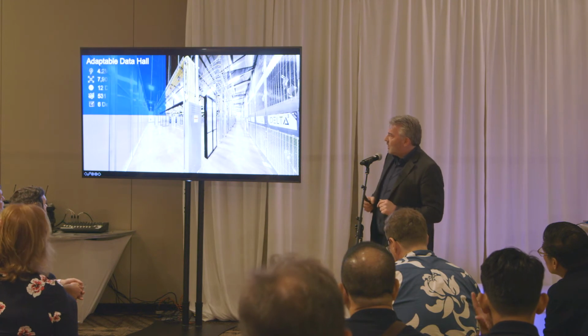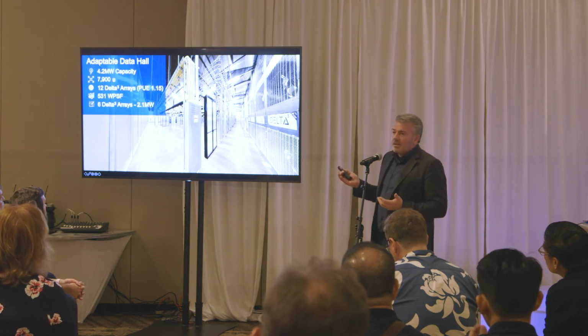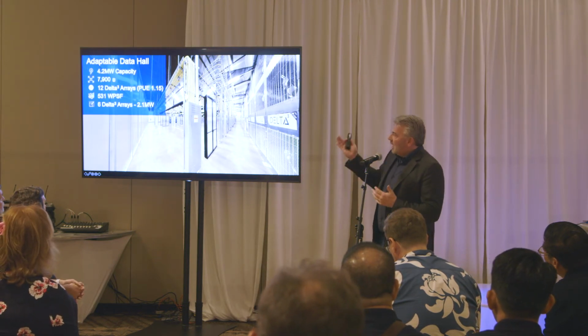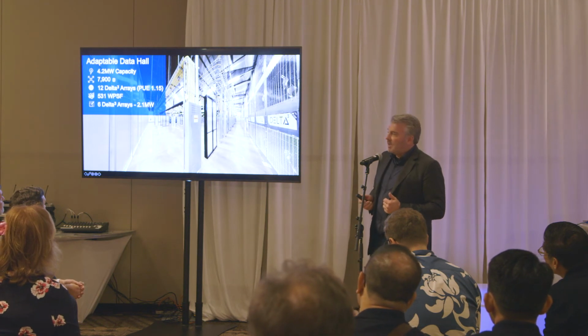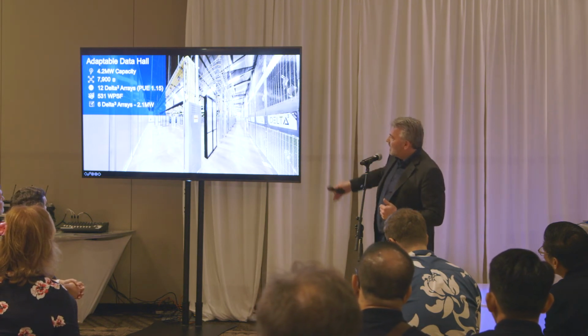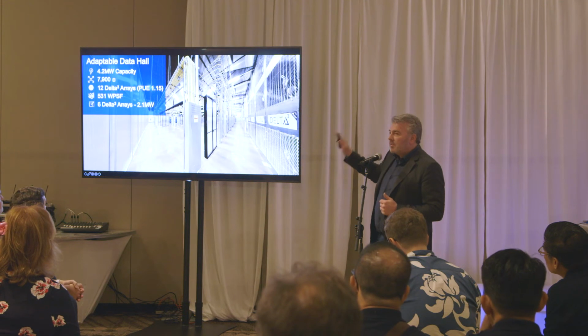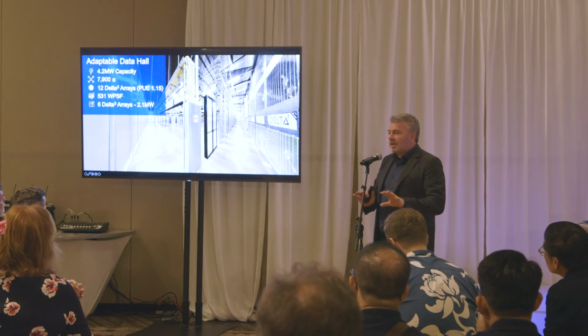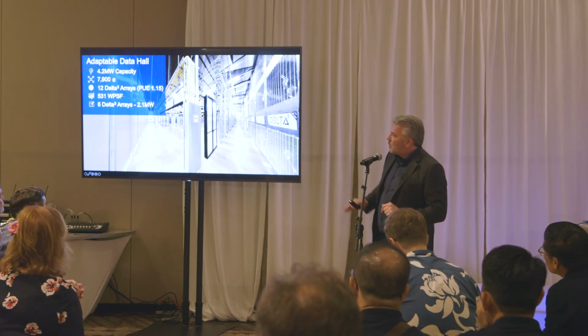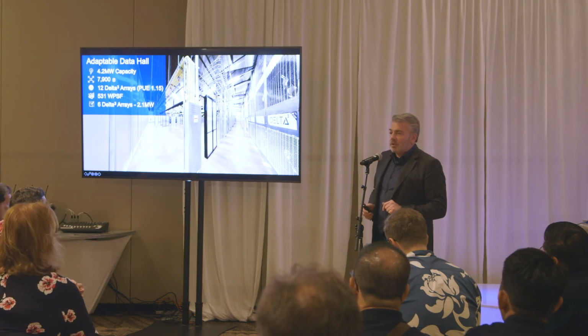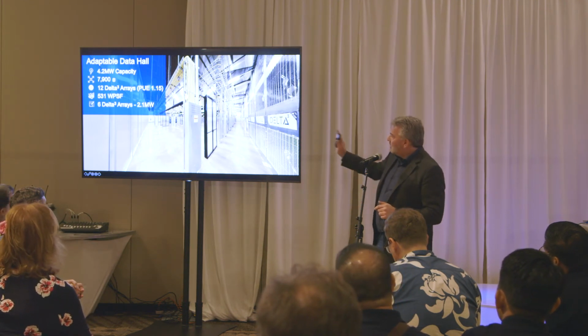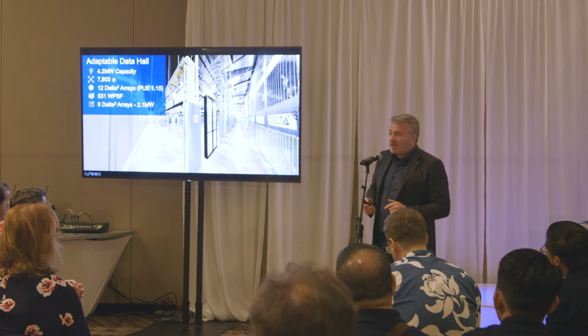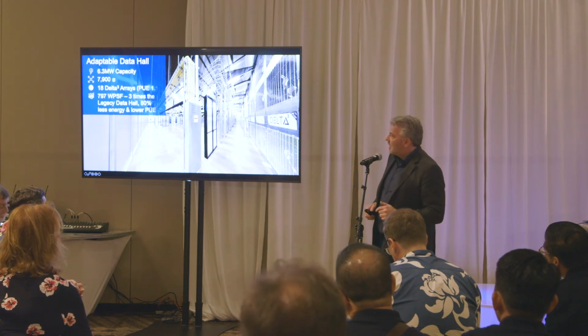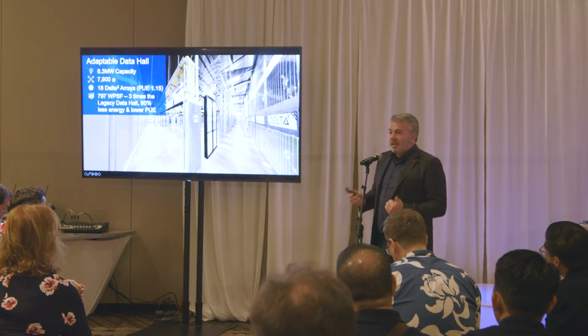This particular one is designed as a 4 megawatt data hall, less than 8,000 square feet. Because of the cooling system here, the PUE is much, much lower, so that's energy cost savings. We're looking at twice the capacity in terms of watts per square foot. There are also provisions to put another 6 cooling devices in, which brings you up to 3 times the cooling capacity in this data hall.